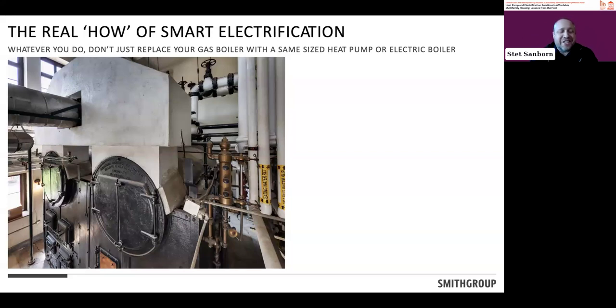I know there are questions in the chat about the issue with the grid. Electric boilers are very peaky, with a very high draw in an instant moment because they're not that efficient. As David pointed out, an electric boiler is effectively a water-based toaster — every time you need heat, you're plugging in a toaster and flipping it on full. It's challenging for the grid to mitigate those spikes, and the system is likely also very much oversized.